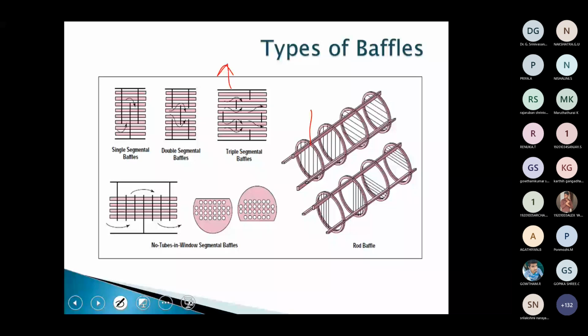In the plate type, you can see the single segmental baffle. Single segmental means the baffles are in a line: this is the first baffle, second, third. Double segmental means there will be a baffle at top and bottom, and the next one will be at the center, then again top and bottom, and then center. So it goes like this. This is called double segmental baffles. Whereas in triple segmental baffles, you can see the center, and then it goes like this. These kinds of baffles are provided, and the ultimate aim is to enhance the rate of heat transfer.